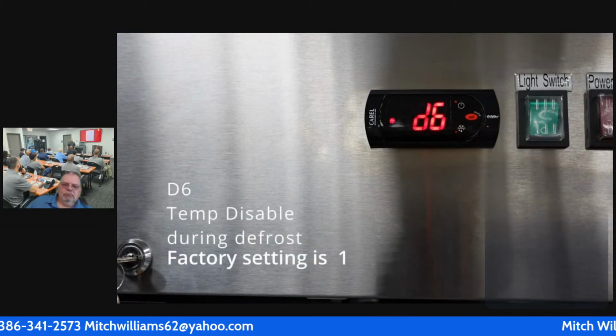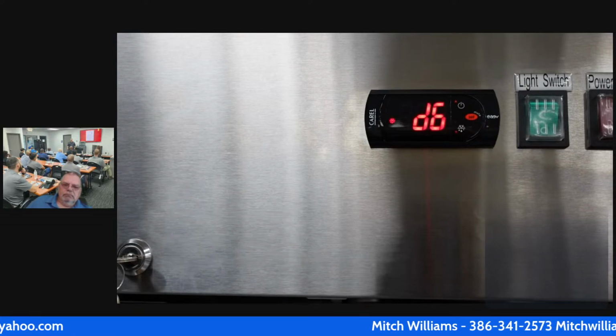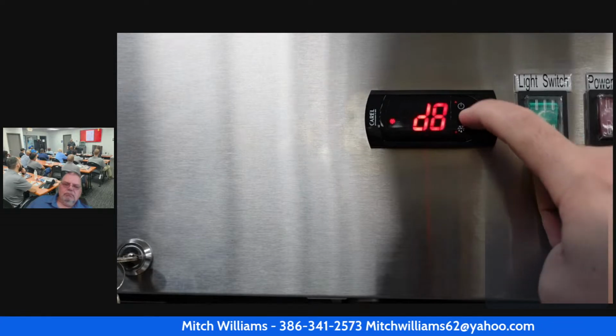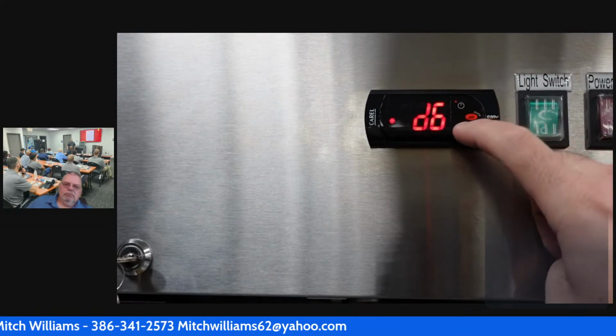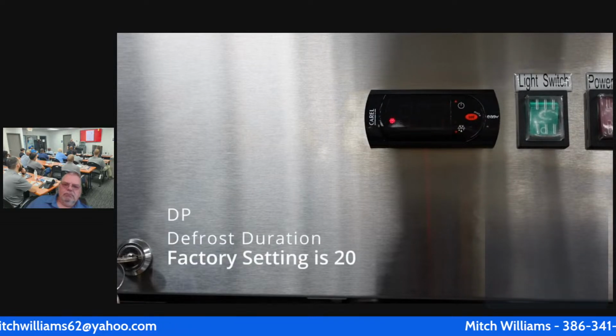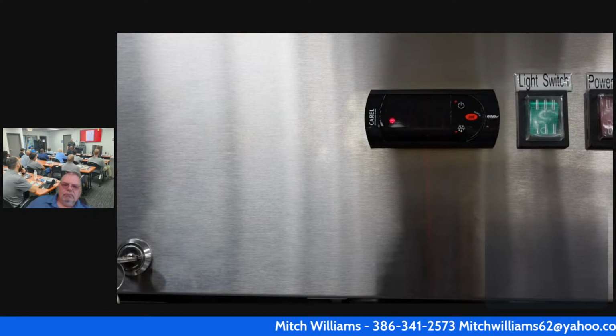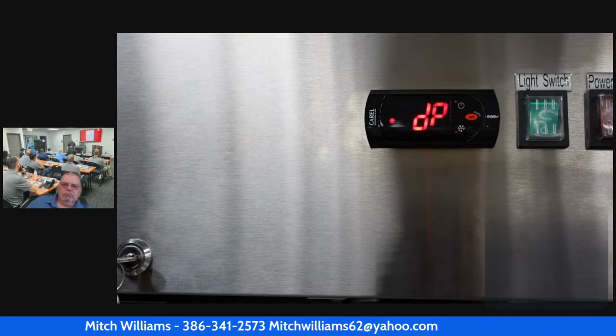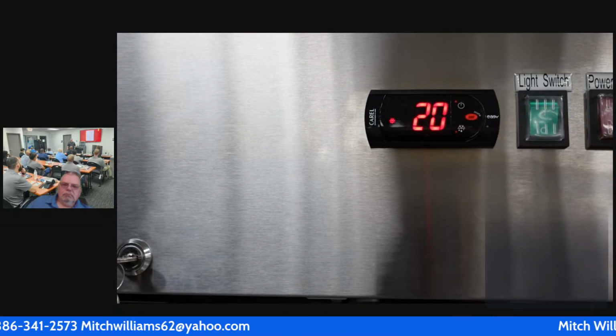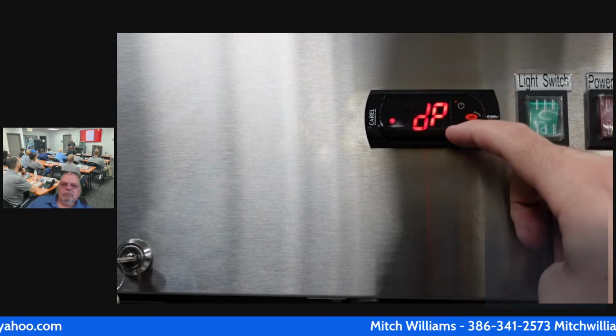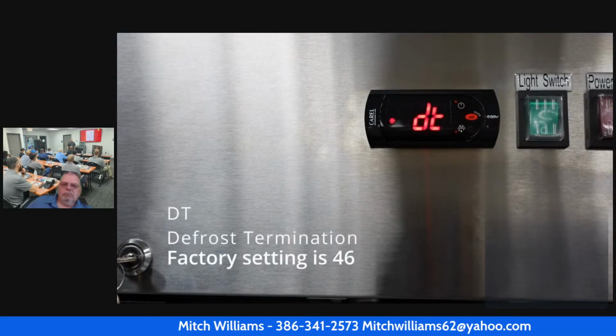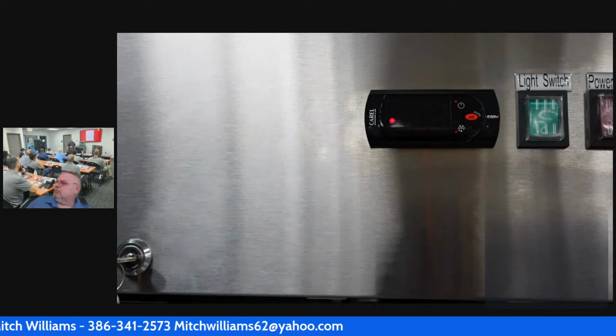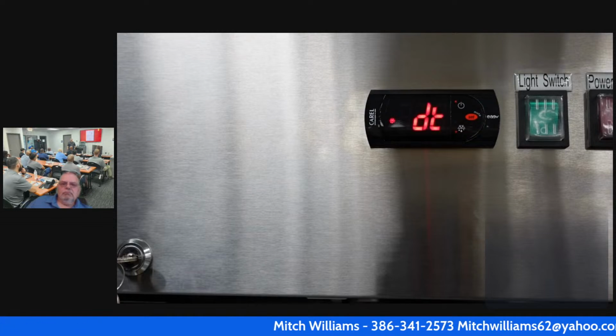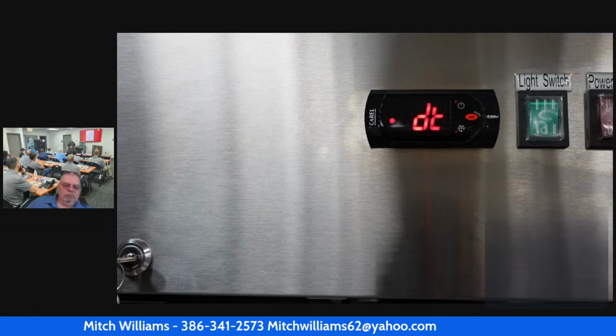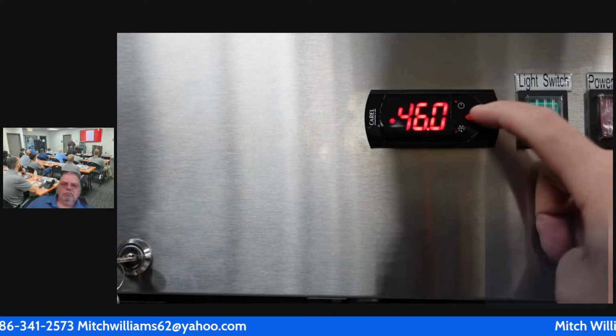The next one you'll see is D6. D6 will allow you to disable the temperature during a defrost. The factory setting is 1. The next parameter you'll see is DP. DP is the setting to control the defrost duration, which means how long the unit will go into a defrost cycle. The factory setting is 20, meaning 20-minute defrosts. The next one we'll see is DT. DT is the defrost termination temperature, meaning once the temperature sensor reaches a certain temperature, it will come out of a defrost. If the unit reaches this temperature before the 20-minute defrost cycle is over, it will force the unit out of a defrost. The factory setting is 46 degrees.